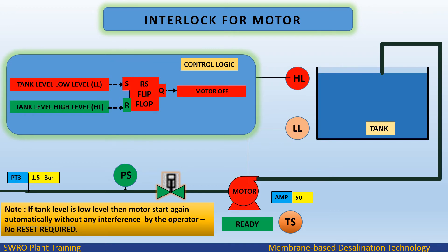When tank level high is active, it resets the RS flip-flop and the motor turns off. Note: if tank level drops to low level again, the motor starts automatically without any operator interference — no reset required.